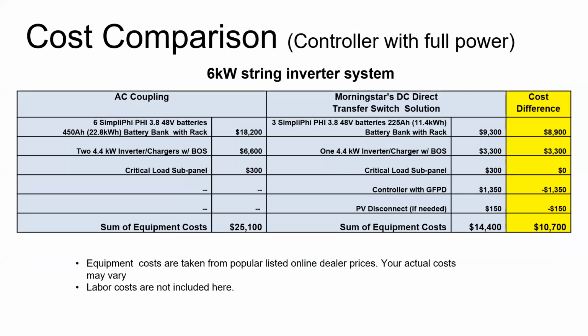When we're AC coupling, let's say we have a 6 kilowatt string inverter, or array. Now we're tied to that 6 kilowatts plus probably a 1.25 adder, and that's what we need to base our multi-mode battery-based inverter size off of. In that case we'd need a minimum — let's say our inverter is a 4.4 kilowatt inverter charger, a battery-based charger — we would actually need 2 of those.